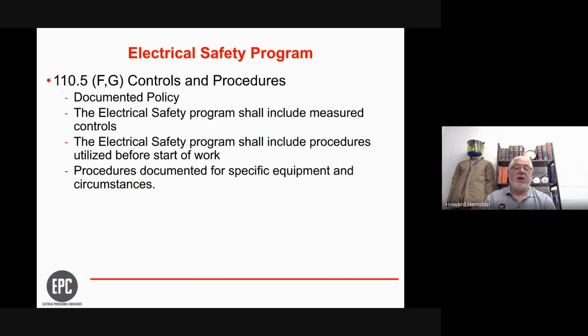If there's specific equipment and specific circumstances that I need to look at, I need to make sure I have well-documented procedures that have been reviewed with the owner and the general contractor, so we are following specific guidelines, such as if we're working on equipment affected by water or steam, I need to control those energies before I shut the power off and create bigger problems.